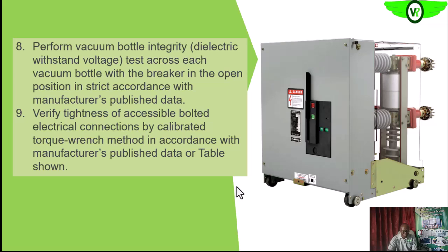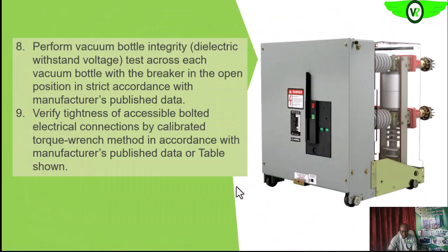So we want to be sure that the vacuum bottle integrity is intact. All those electrical connections that are accessible, we want to verify that they have the appropriate torque on them, that they are tight and firm. We want to use a calibrated torque wrench and be sure that we apply the appropriate torques. Those are some of the things we need to check to ascertain the integrity of our vacuum circuit breaker, so that we can release it back into operations.